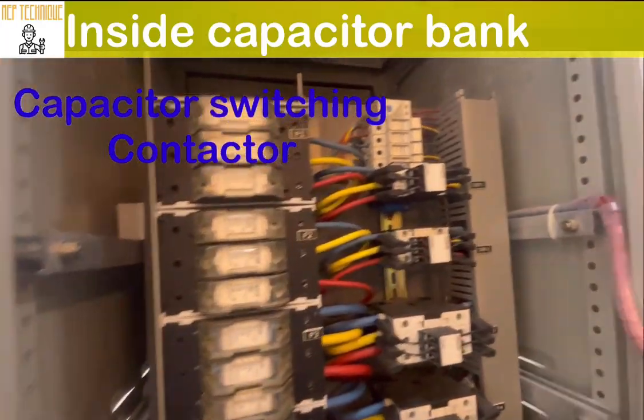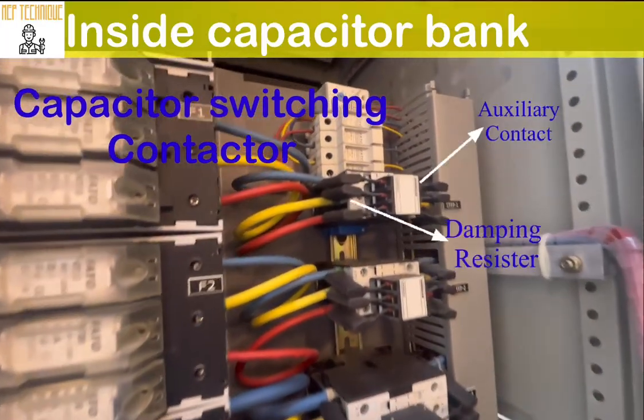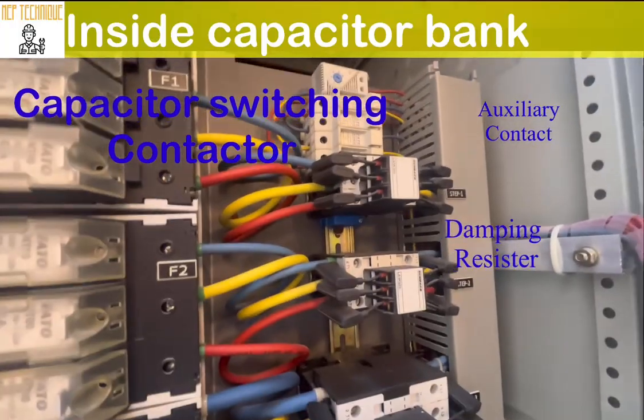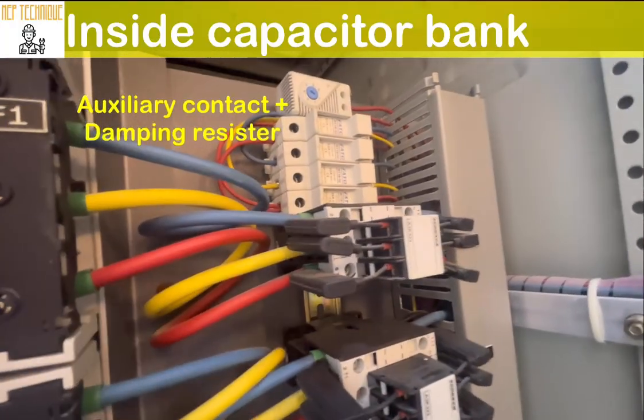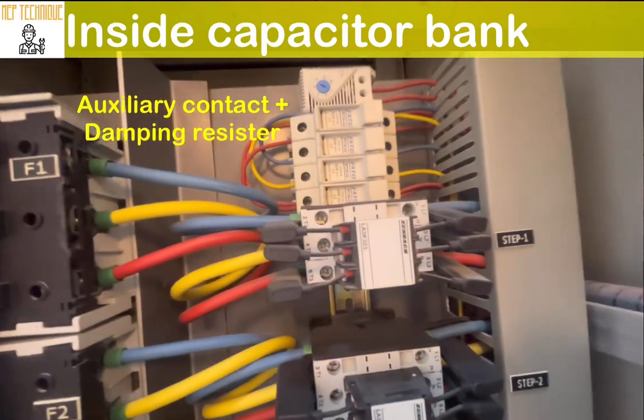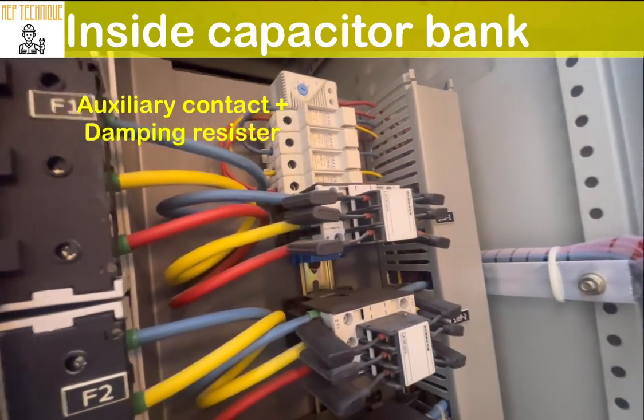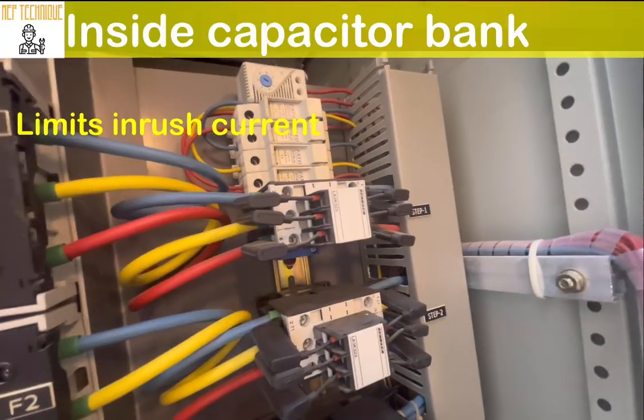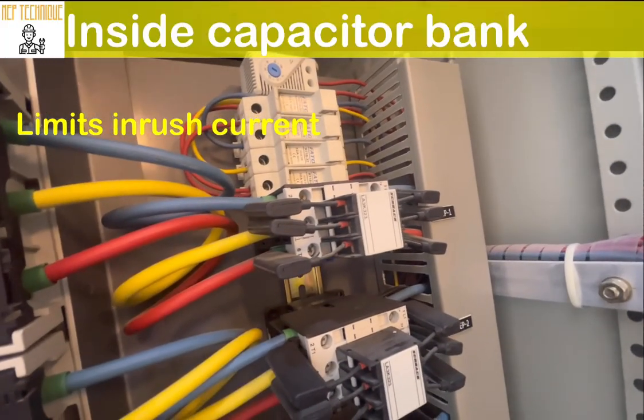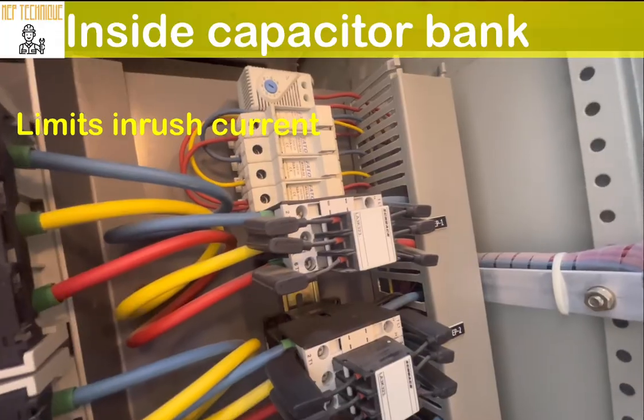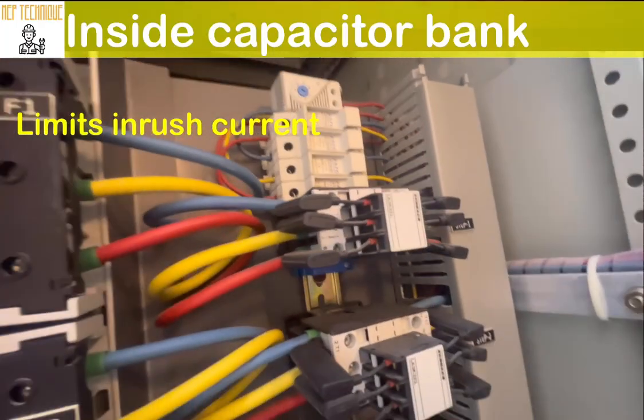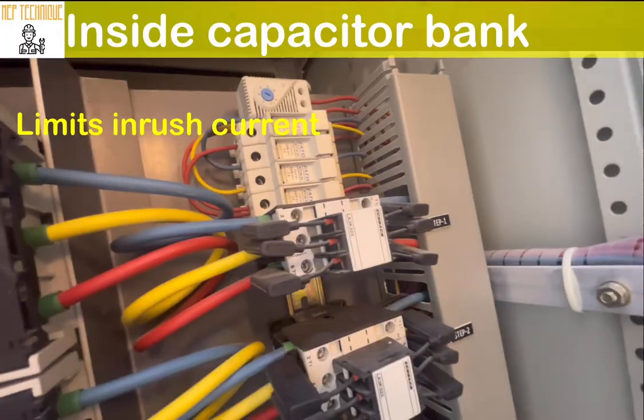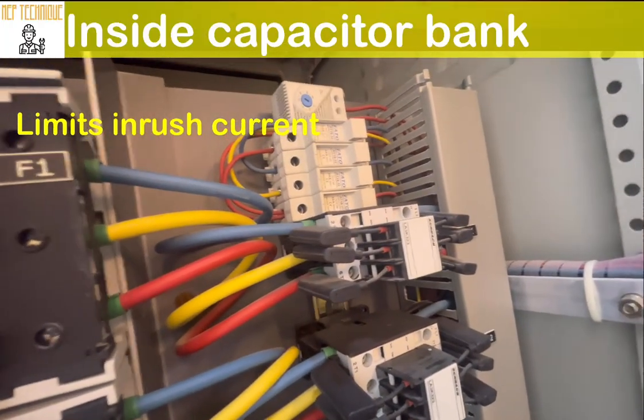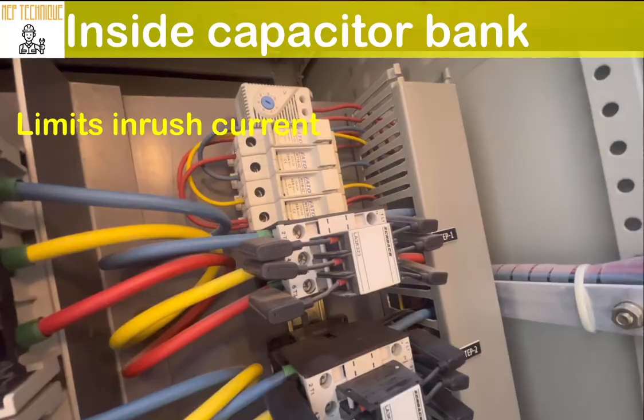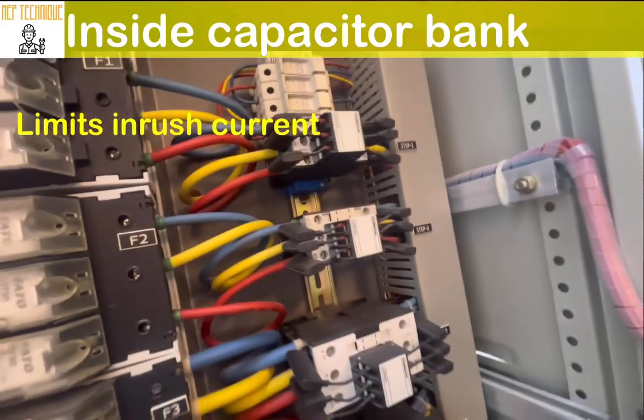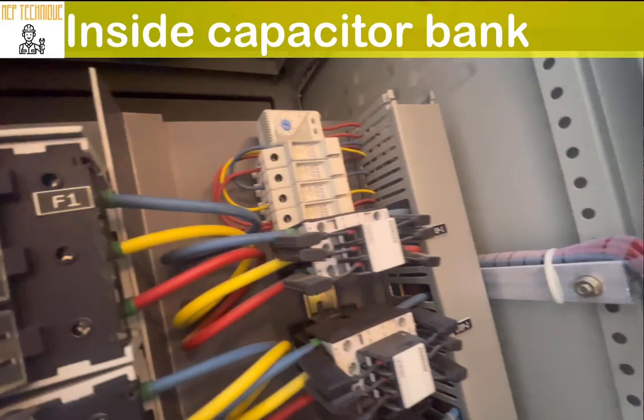So after the fuse, it is connected with the contactor. You can see there is something new you will find here. Over the contactor there is an auxiliary contact and a resistor connected here. So what is the reason behind this? As you know, the auxiliary contactor closes slightly faster than the main contactor when connecting the capacitor through a pre-charge or damping resistor. Why do we use this? Because it will limit the high inrush current when the capacitor is energized. Okay, that's why we use the auxiliary contact.